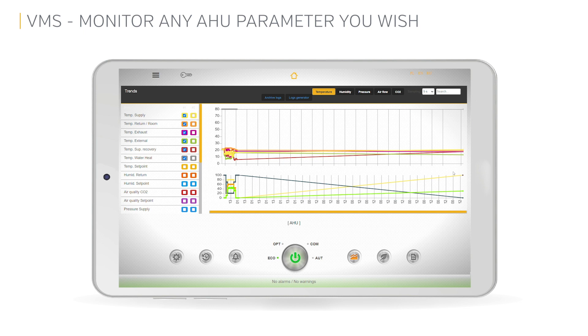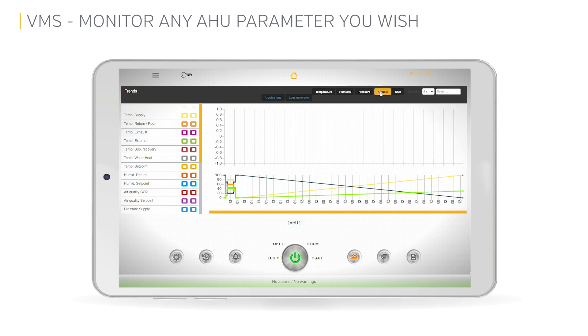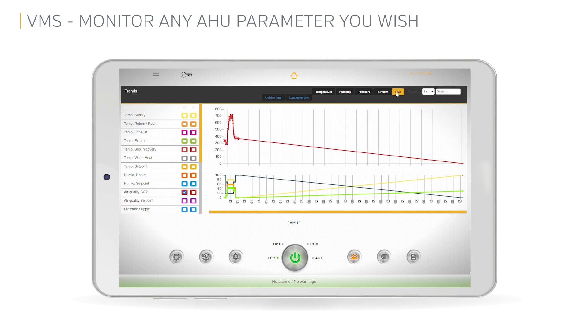What are the benefits of watching selected AHU parameters and their history? For example, you can find the best threshold of accepted CO2 level in the return air at which the mixing box of your unit remains fully or partially open, allowing your fans to run on the lowest possible static pressure. It's easy to deduce that engaged recirculation brings significant savings — zero electric power consumption.